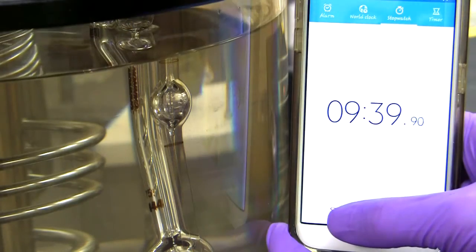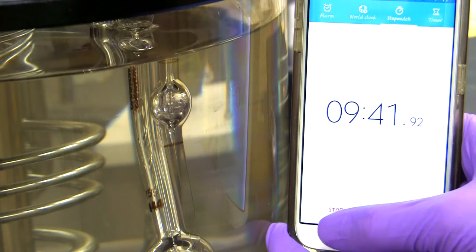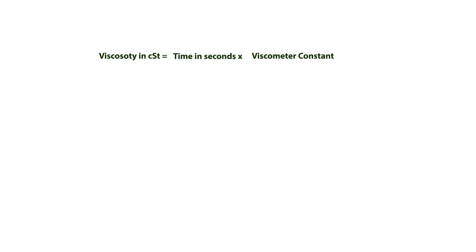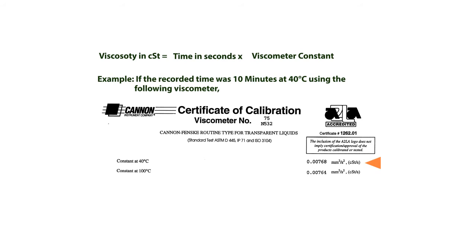Calculate the kinematic viscosity in millimeters squared per second or in centiStokes of the sample by multiplying the efflux time in seconds by the viscometer constant. Repeat the test and calculate the kinematic viscosity again. Average the values to report the kinematic viscosity of the tested fuel.